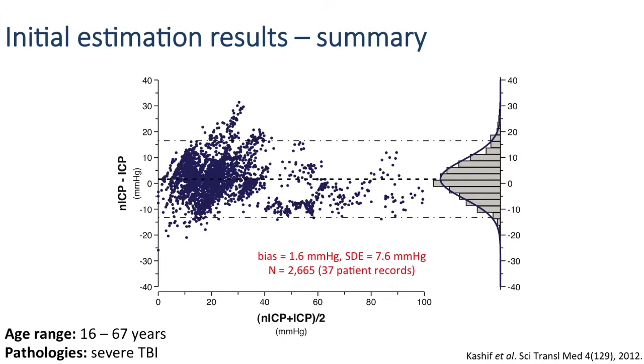The question that arose now was, how do we take something that has a standard deviation of the error of 8 millimeters of mercury, and shrink that down to a standard deviation of the error, ideally, of about 4, maybe 3 millimeters of mercury? Because the transition zone is between 15 and 20, or 15 and 22 millimeters of mercury. This is the level of ICP that we would like to resolve on a patient-by-patient basis. So it's not enough to do well on average. We have to be able to do well in the individual subjects.